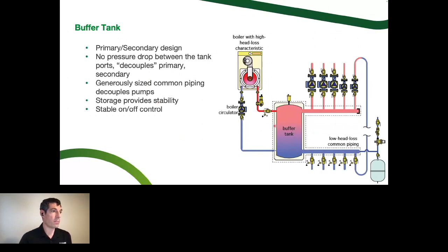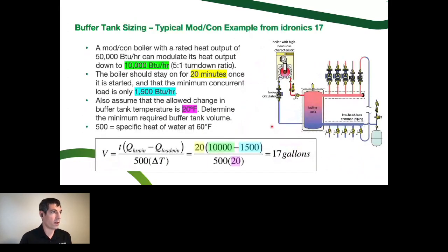So this is something that provides some additional benefits. There's a formula that we've got in idronics 17 that can go into a little bit more detail for, well, what size buffer tank are we talking about here? And these are the different variables that we have to know to size the minimum buffer tank for what we're looking to do. So if we say that we have a 50,000 BTU boiler that can turn down to 10,000 BTU, so it's got a 5-to-1 turn down ratio, we would like that equipment to be on for a minimum of 20 minutes each time that it fires. So that would be great for the cycle efficiency of the system and to make sure that the energy efficiency of every BTU of gas or every unit of electricity that we're using is put to good use and not, in a gas scenario, just going up and out the flue every time we go to a post-purge, pre-purge cycle. And then we need to know something about the system.